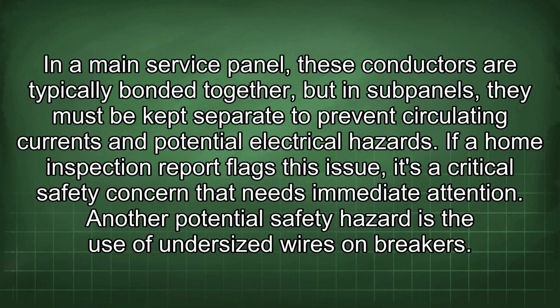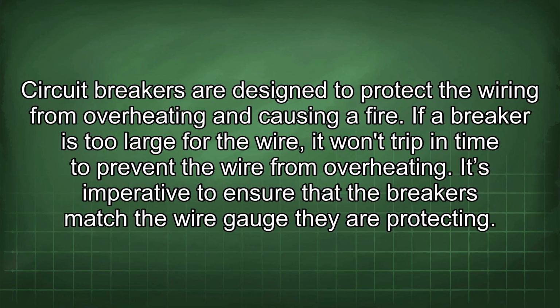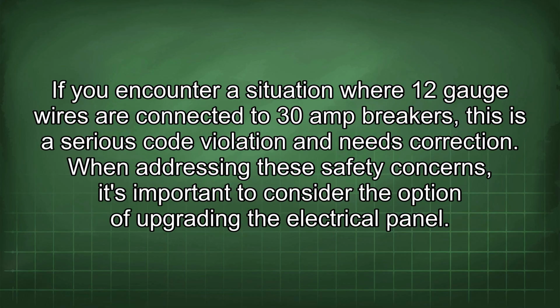Another potential safety hazard is the use of undersized wires on breakers. Circuit breakers are designed to protect the wiring from overheating and causing a fire. If a breaker is too large for the wire, it won't trip in time to prevent the wire from overheating. It's imperative to ensure that the breakers match the wire gauge they are protecting. If you encounter a situation where 12-gauge wires are connected to 30-amp breakers, this is a serious code violation and needs correction.